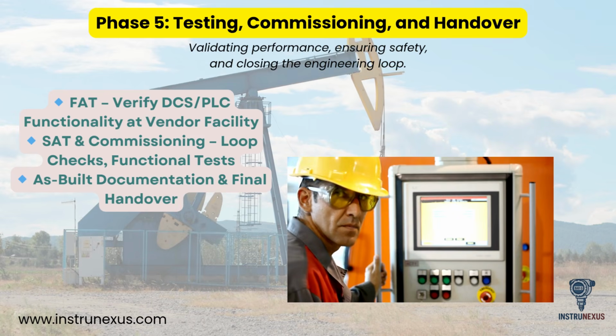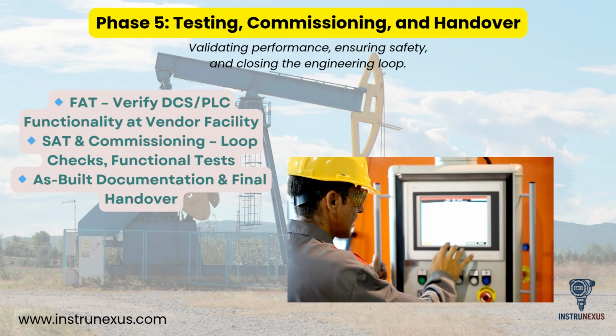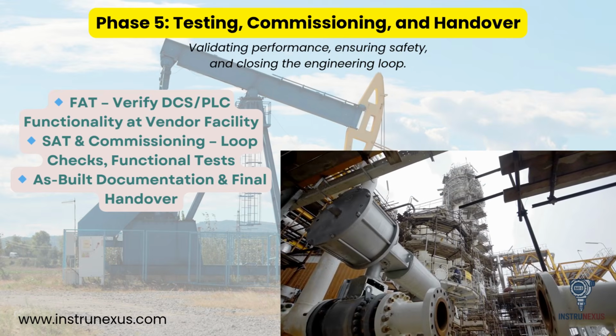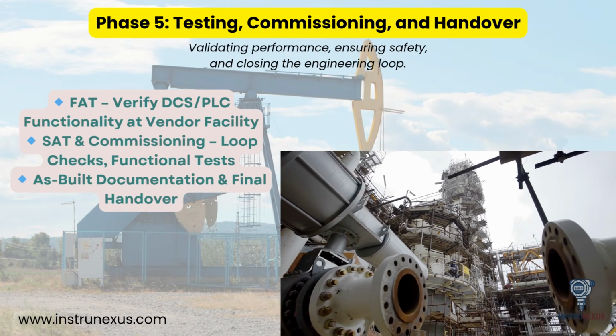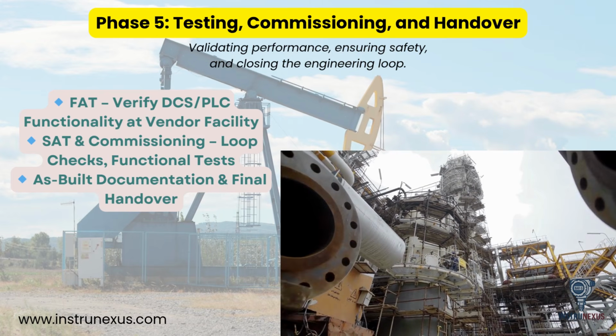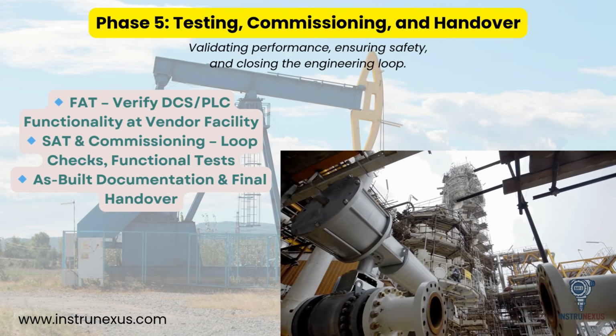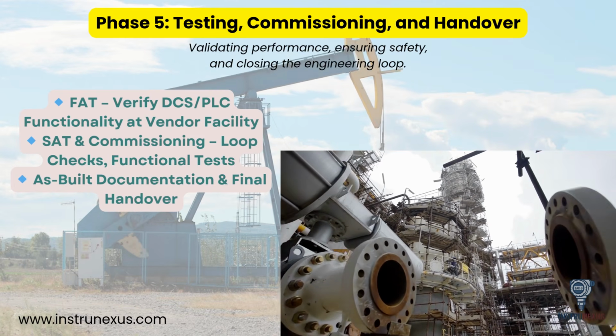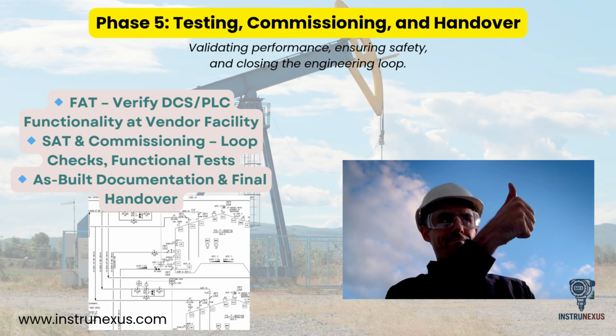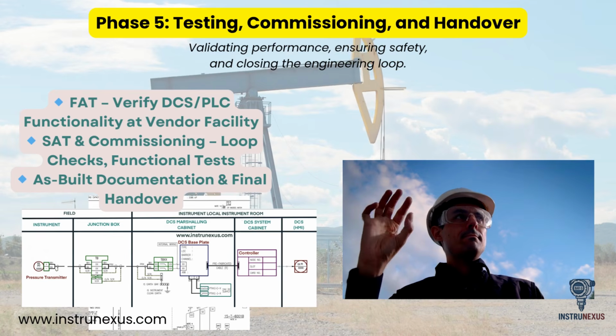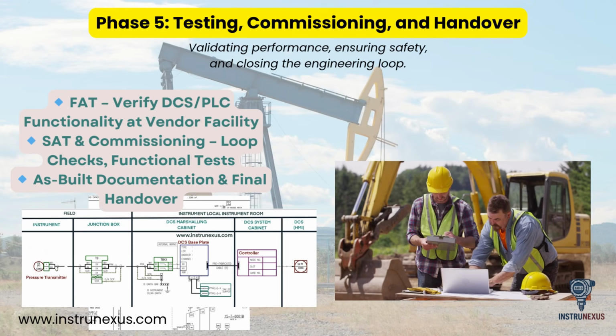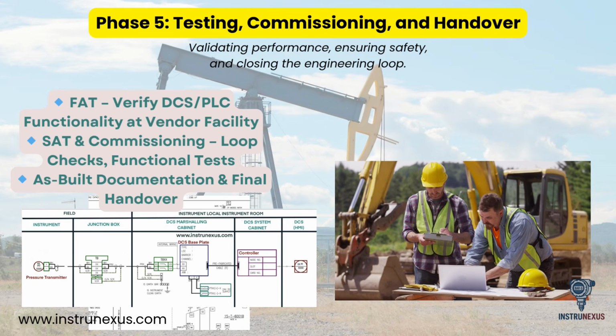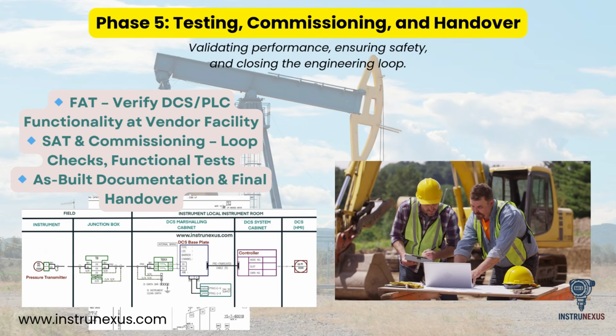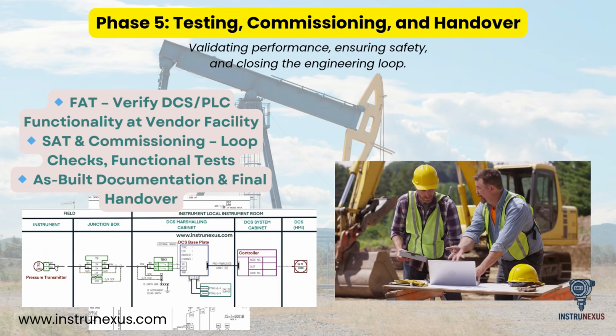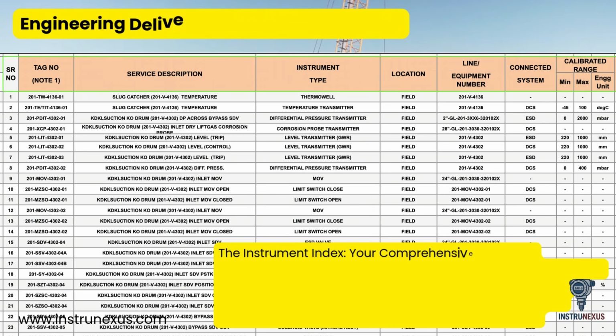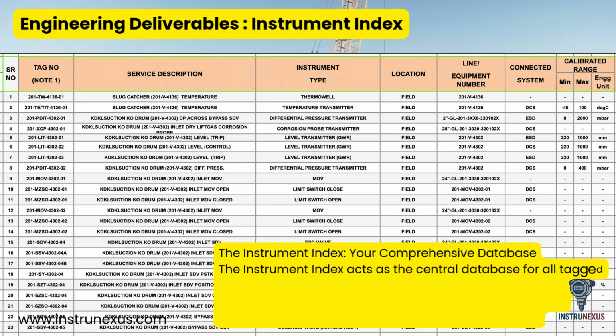Once the system is installed, engineers conduct the Site Acceptance Test, or SAT, along with loop checks and functional tests, confirming that all field devices, interlocks, and control strategies operate correctly in the plant environment. Finally, the documentation phase ensures that every drawing and record, from P&IDs to loop diagrams and instrument indices, is updated to its as-built or reissued for construction status. This marks the official handover, delivering a system that is tested, documented, and ready for safe, reliable operation. The instrument index serves as the master database for every tagged instrument within a project.